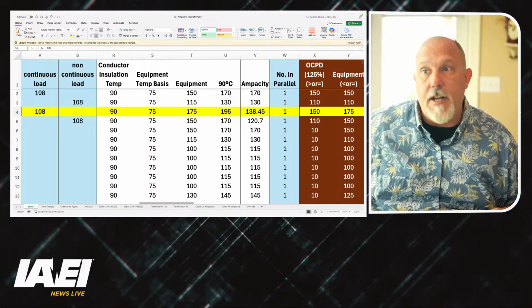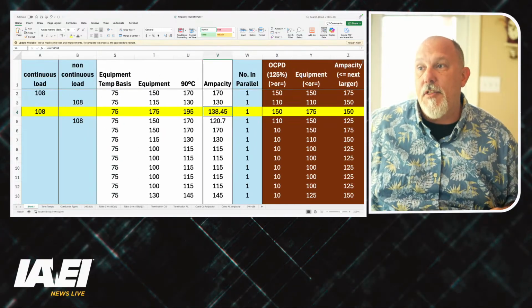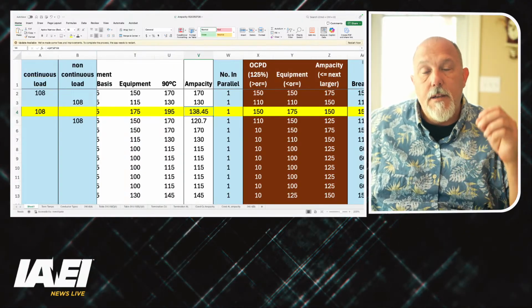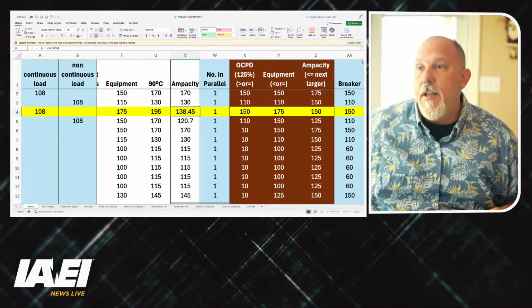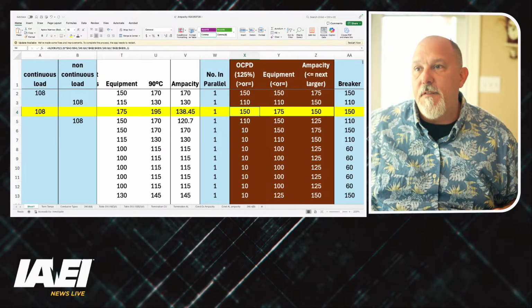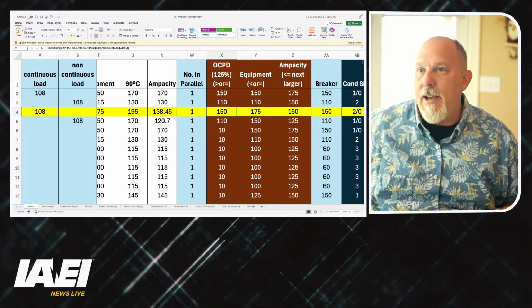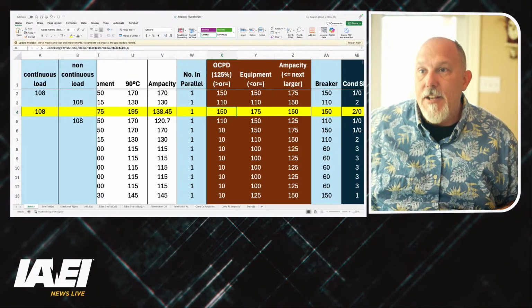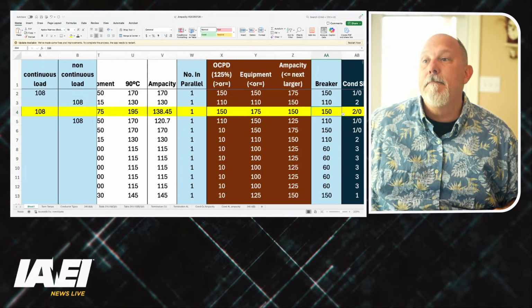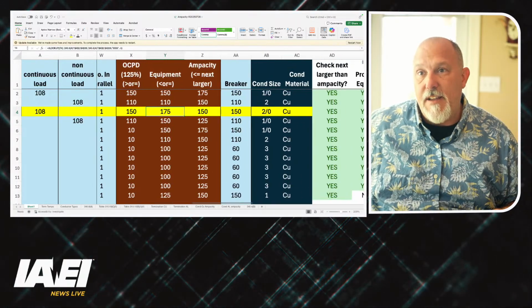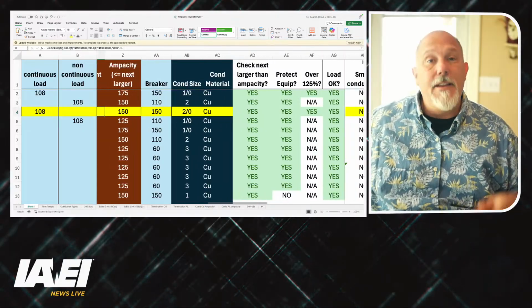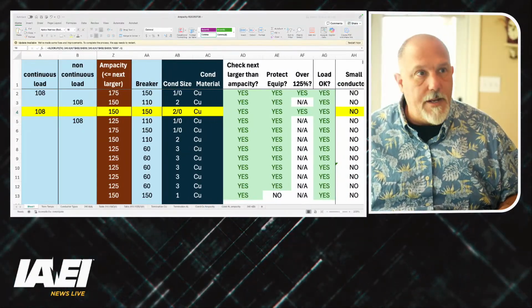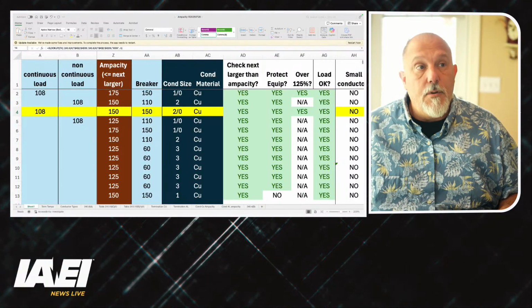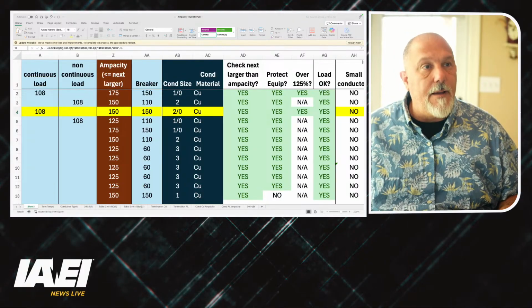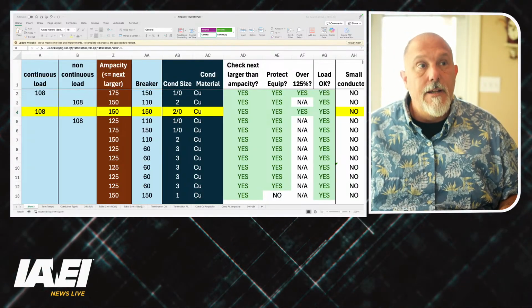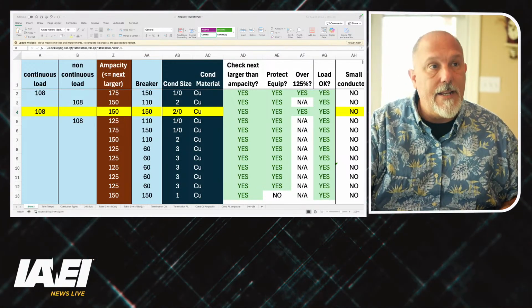That brings the numbers for the conductor up. The ampacity is now 138.45 because I multiply the table by the conditions of use. The overcurrent device has to still be greater than 135 amps, but my ampacity value now is less than or equal to 150, so I can put a 150 amp breaker on it, and I'm still less than the equipment rating of 175, and I meet all my criteria. So now we have that ironed out. Now we're going to go to UL 489, and let's take a look at the table for a 110 and 150 amp breaker, and make sure that our selection aligns with how we test overcurrent devices.